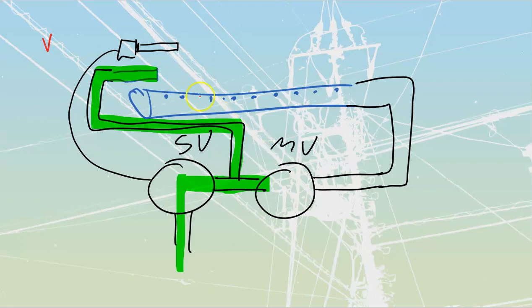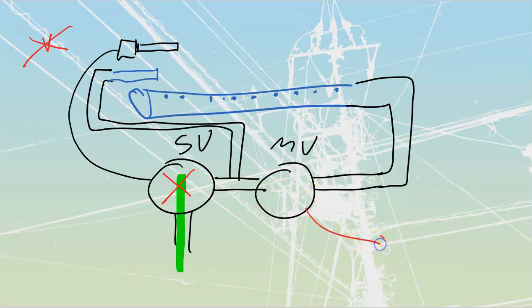If, for whatever reason, it goes out, this thing will cool, and when it no longer has heat, it can no longer convert that heat into electricity, so I will no longer have voltage, which means that this will now go and shut off my safety valve, taking out the gas. So there's no gas leaking in, which is great, because right now if I would call for heat otherwise, I would be able to call for heat with no pilot light. I'd be able to dump large amounts of gas out into the atmosphere of whatever my installation is going to be. So this is going to be a flame-proving device.